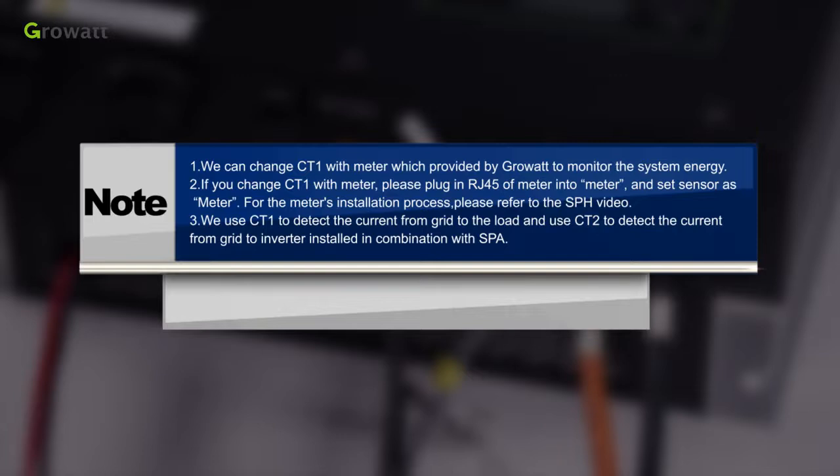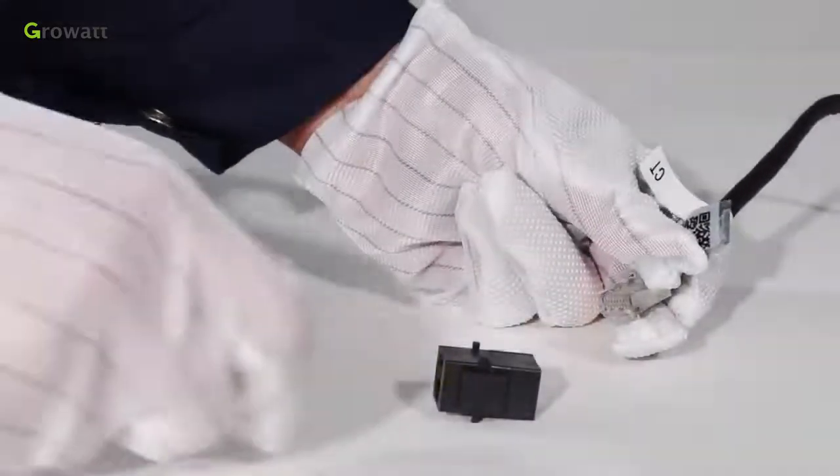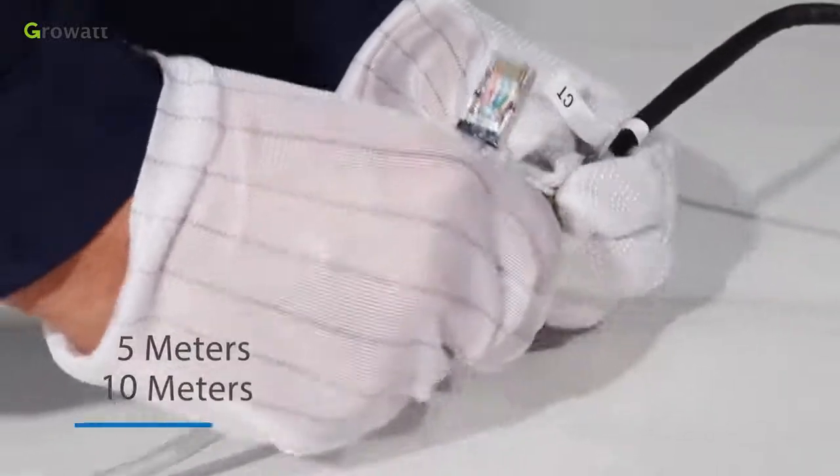Note 1. We can change CT1 with meter which provided by Growatt to monitor the system energy. 2. If you change CT1 with meter, please plug in RJ45 for meter into meter and set sensor as meter. For the meter's installation process, please refer to the SPH video. 3. We use CT1 to detect the current from grid to the load and use CT2 to detect the current from grid to inverter installed in combination with SPA. 4. Growatt provides two cables whose length is 5m and 10m.